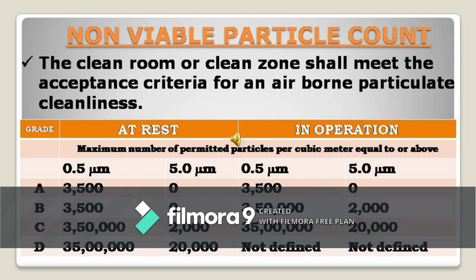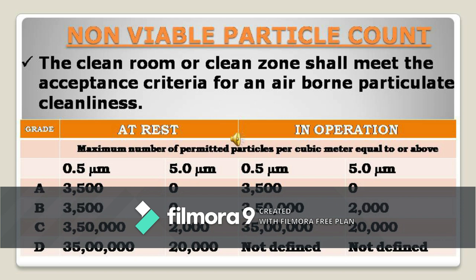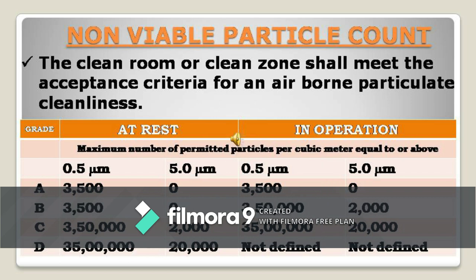Next, we perform the non-viable airborne particle count test. You need a particle counter for this, and it should be duly calibrated with a national or international traceability certificate — this is mandatory for master equipment. For the number of locations and acceptance criteria, we use a stringent combination of ISO, EU, and WHO GMP guidelines. This table shows the criteria for at rest and in operation for all grades.